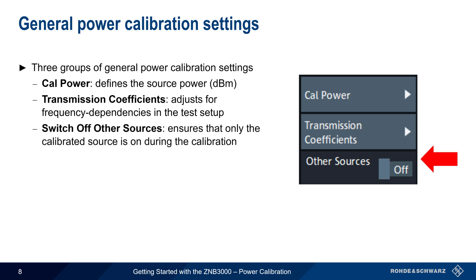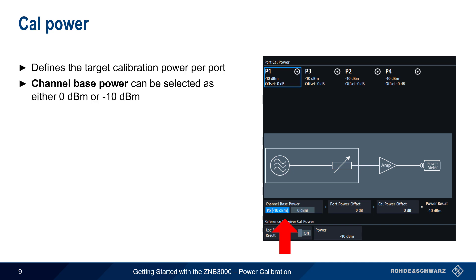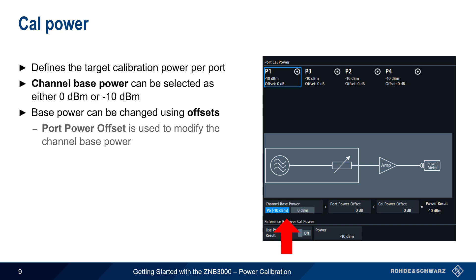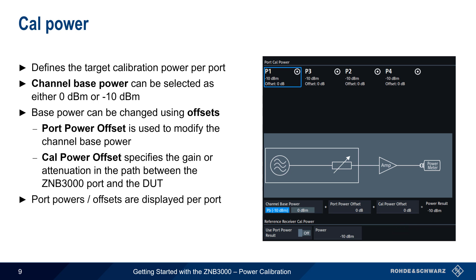CalPower defines the target calibration power and is configured individually per port. The channel base power can be selected as either 0 or minus 10 dBm. This base power can then be changed using two different kinds of offsets. The first is the Port Power Offset, which is simply used to modify the channel base power. The second is the CalPower Offset, which is used to specify the amount of gain or attenuation in the path between the ZNB3000 output and the device under test. The Port Power and Offsets are displayed on a per-port basis at the top-left portion of the dialog.